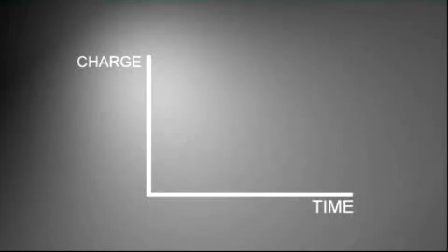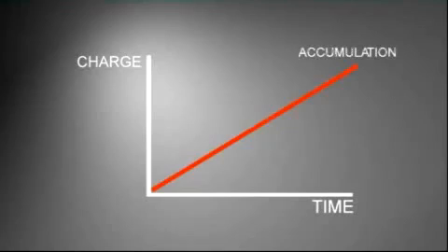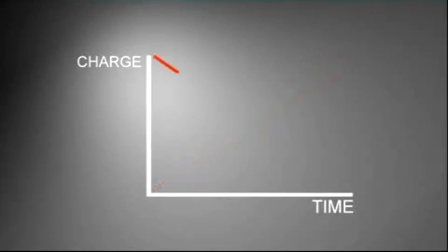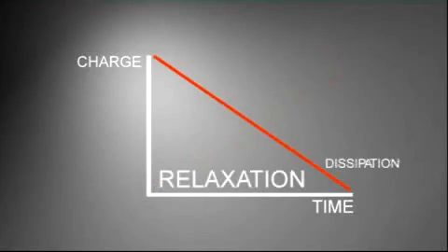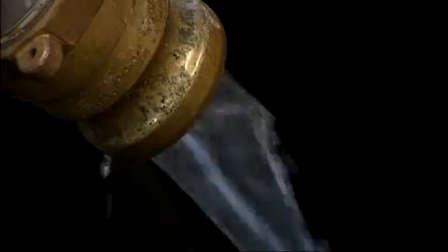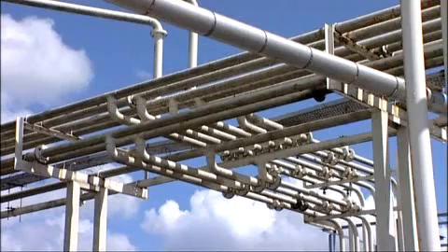The amount of charge remaining after a given time depends on the amount generated and the amount dissipated. The time required to ensure the charge dissipates to a safe level is known as the charge relaxation time, which will vary with different solvents. Turbulence experienced in filling operations, caused by large flow rates, splashing, or free-falling liquids, greatly increases the charge accumulation beyond the level generated in pipes.